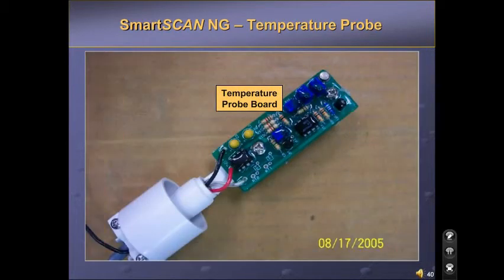Clearly, there are a number of potentiometers on the temperature probe board. These pots are used for calibration at the factory. There is nothing field serviceable on the temp probe board. If the temp probe board fails, it usually goes to one of its max temperatures, minus 40 degrees or positive 149 degrees Fahrenheit. If this occurs, the only option is to change the temperature probe.